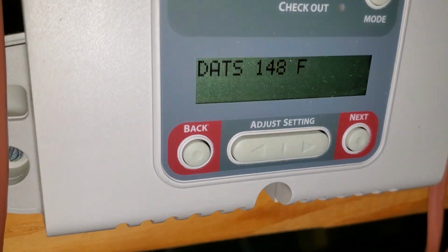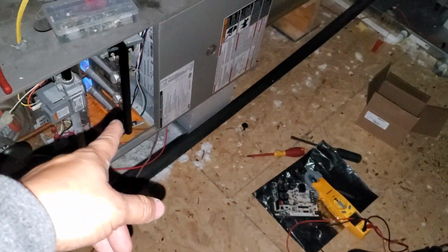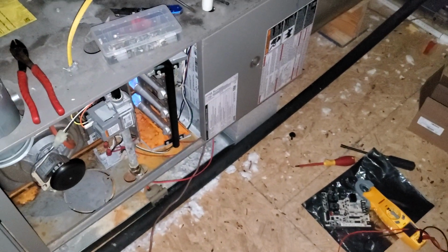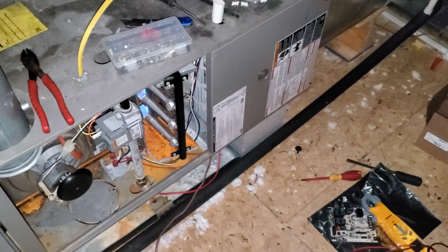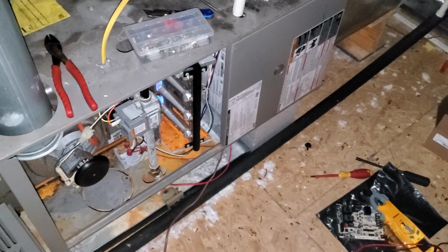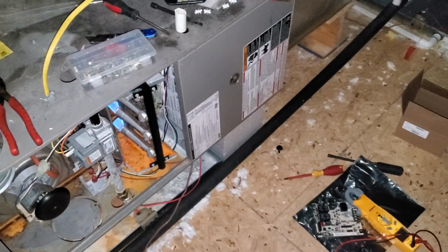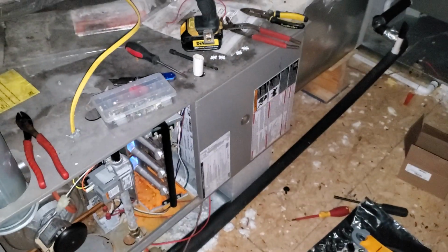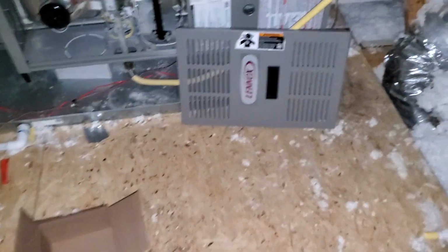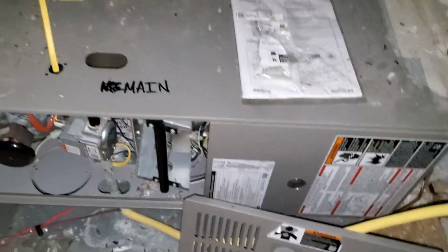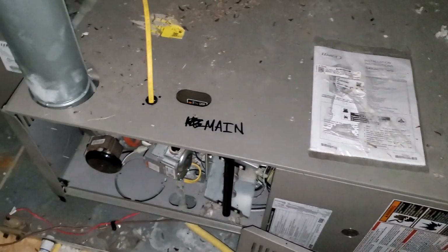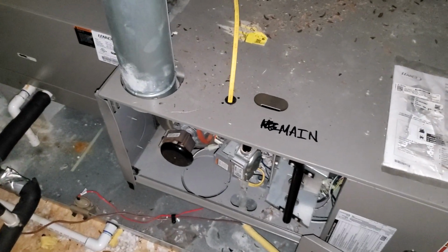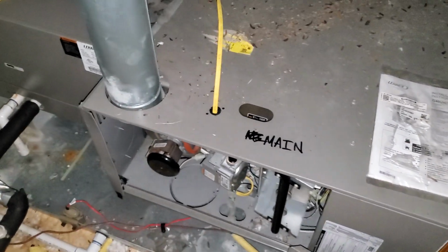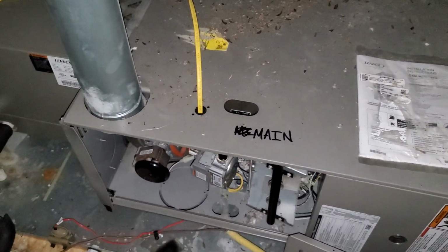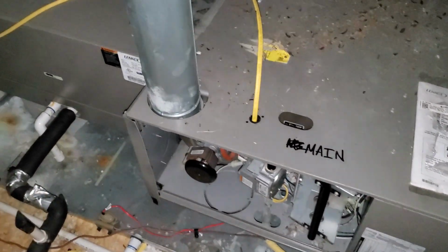Let's see, we're running at 140, 147 and climbing. The temperature rise design for this furnace is 40 to 70. It's about 68 degrees downstairs, so obviously you do the math, we're at the upper end of that. But then we'll come over here to our other furnace, which is not zoned. It says it's the main unit, which came off to me as odd because it's small. Typically the main unit is the larger of the two. 70,000 BTU furnace on a 2.5 ton air conditioner.